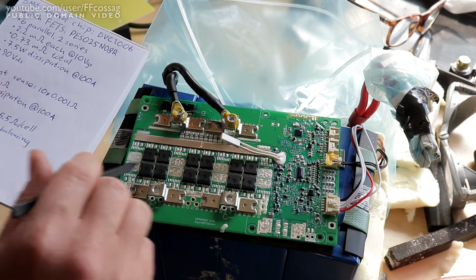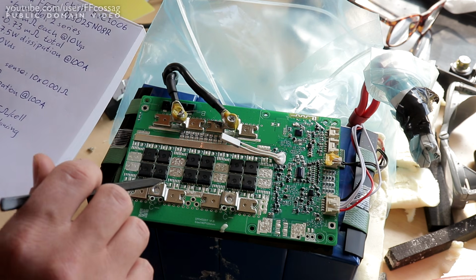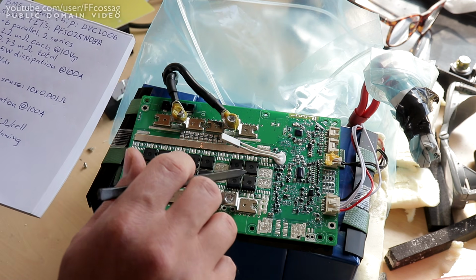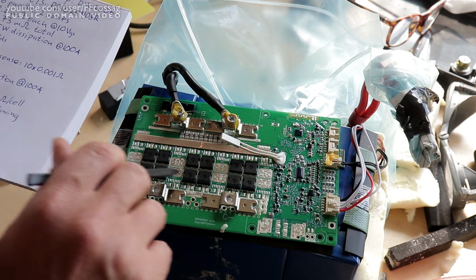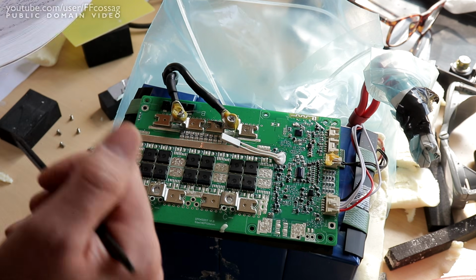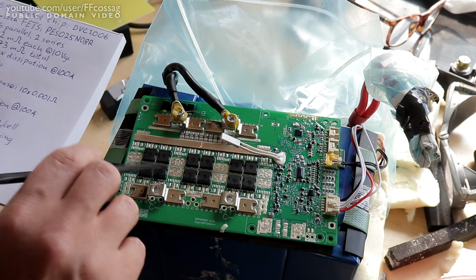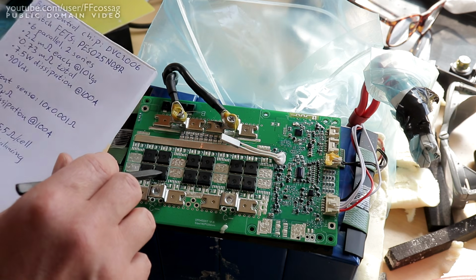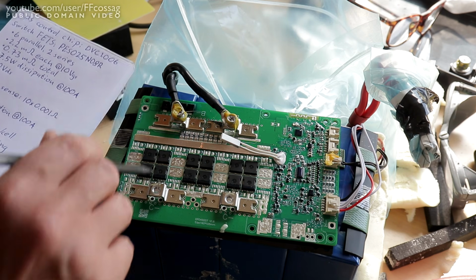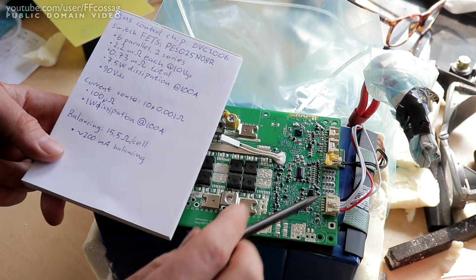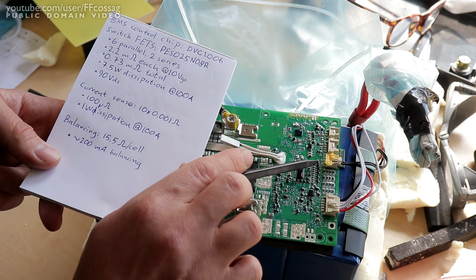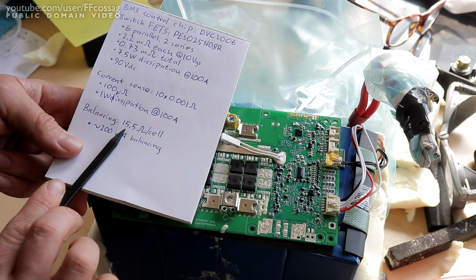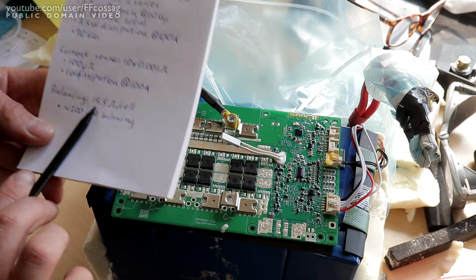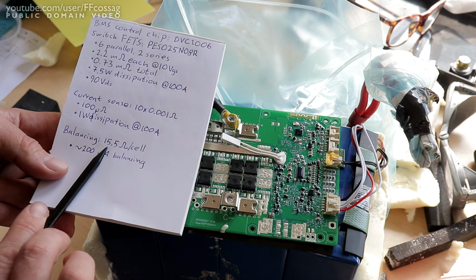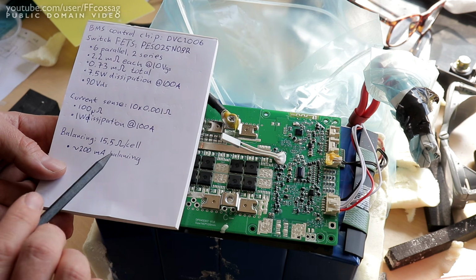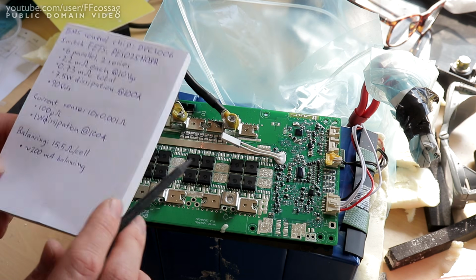These FETs do have a very high surge rating of 1200 amps, so I'm not too concerned with hooking up capacitive loads or switching stuff on. These are pretty hardy FETs, and they do actually have a brand. They're not generic. So I really like the power stage here. Cell balancing is done with these resistors here and this row of transistors. We have 15.5 ohms per cell passive balancing, which is good. That is generally what you want from a safety standpoint. So 200 milliamps balancing, it's completely fine.